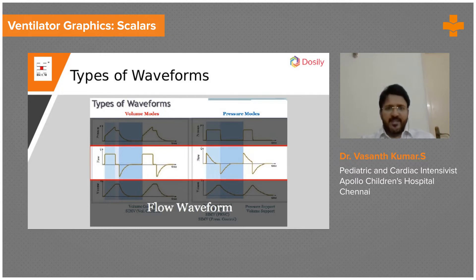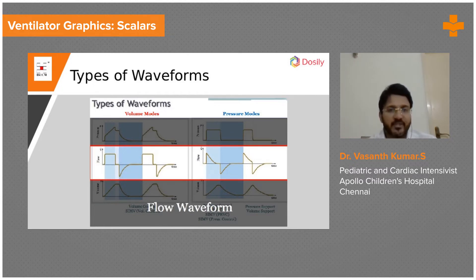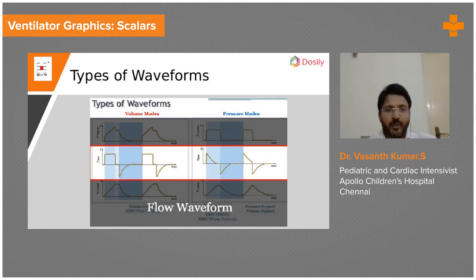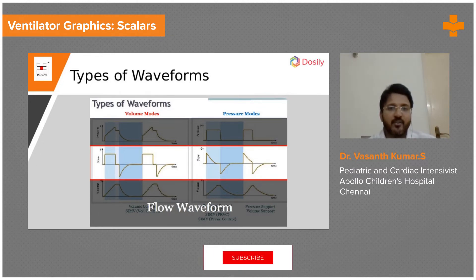The last graph is the pressure-time scalar in volume control mode. Here you set the tidal volume — suppose 100 ml. The ventilator gives a flow; this flow increases the pressure until the 100 ml tidal volume is reached. Once 100 ml is reached, a pause is given. During this pause, the pressure drops and equilibrates between all the alveoli. That is why you see a peak that plateaus before going into expiration.